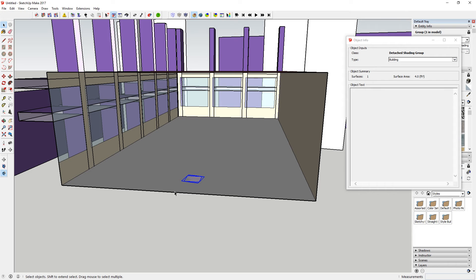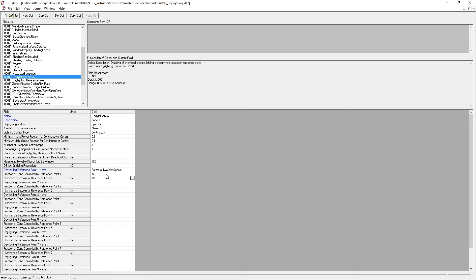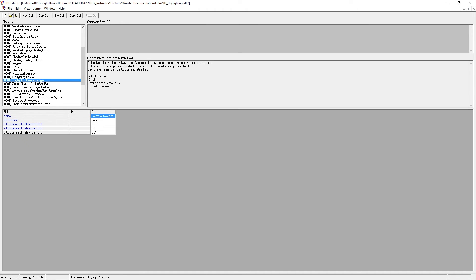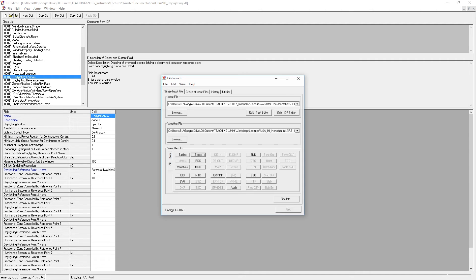So if I wanted to do this scenario, I would go back and I'd change the fraction of the zone to 0.5 or 50% and I'd have to move the reference point for my daylight sensor located here. Now once you've defined the controls and reference point for the sensor, save the file and run it.